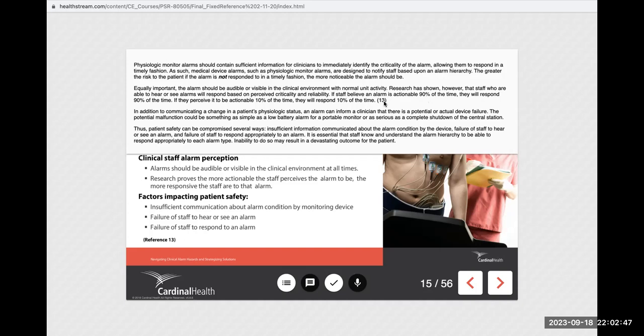In addition to communicating a change in a patient's physiologic status, an alarm can inform a clinician that there is a potential or actual device failure. The potential malfunction could be something as simple as a low battery alarm for a portable monitor, or as serious as a complete shutdown of the central station. Thus, patient safety can be compromised several ways. Insufficient information communicated about the alarm condition by the device, failure of staff to hear or see an alarm, and failure of staff to respond appropriately to an alarm. It is essential that staff know and understand the alarm hierarchy to be able to respond appropriately to each alarm type. Inability to do so may result in a devastating outcome for the patient.